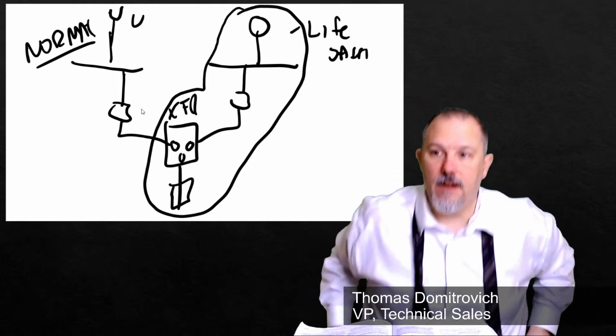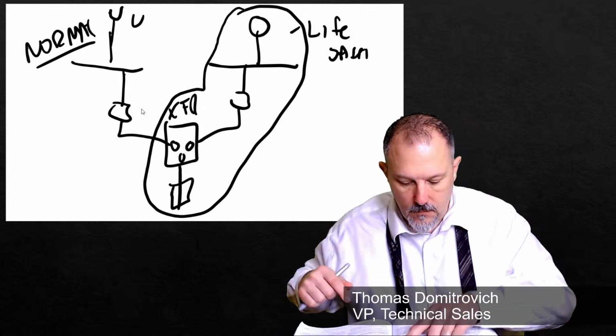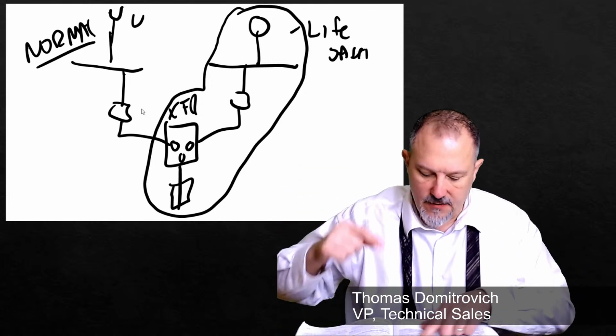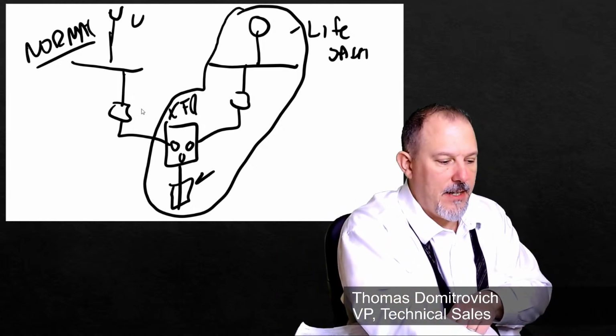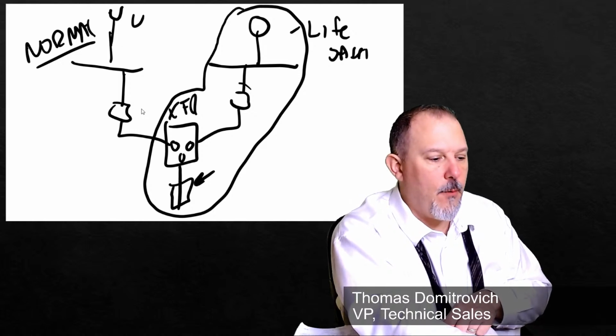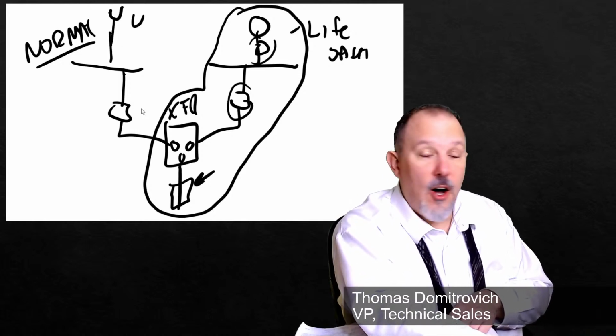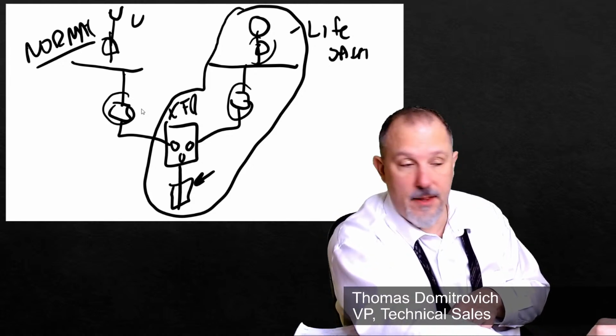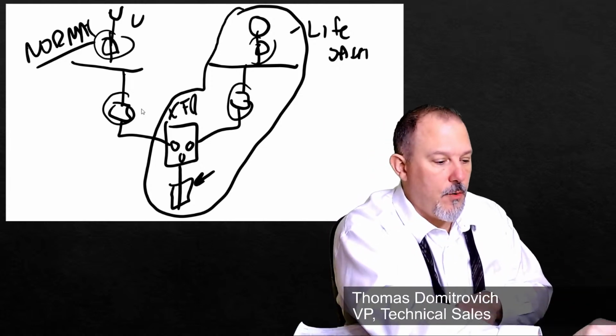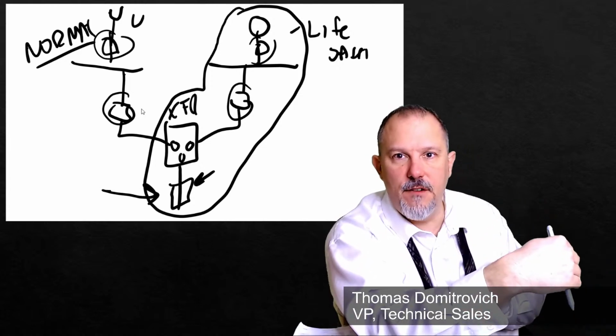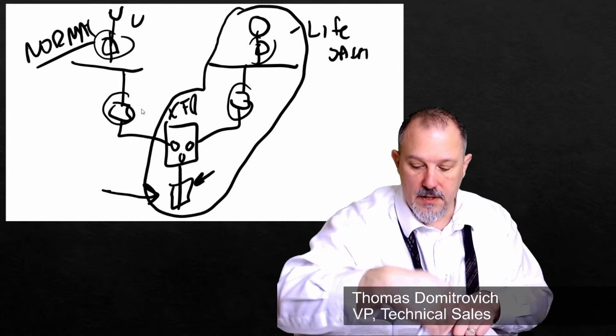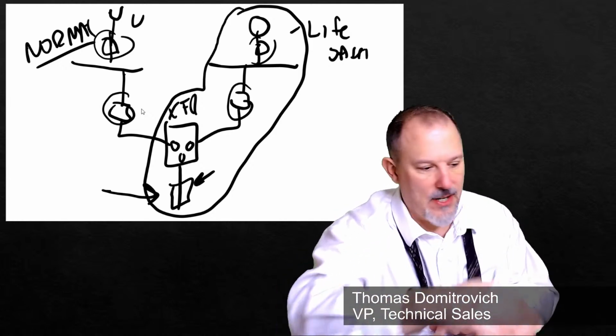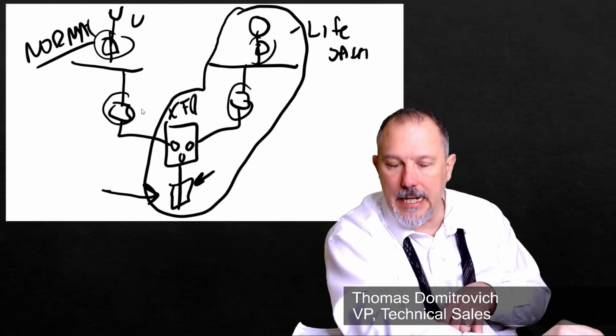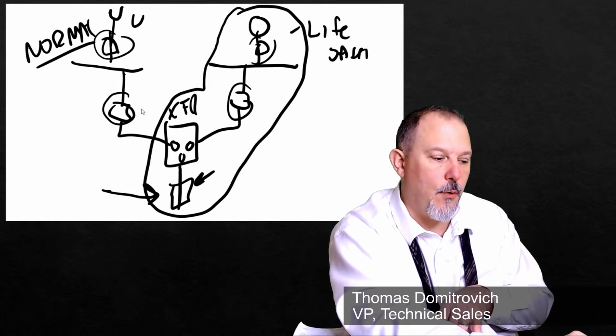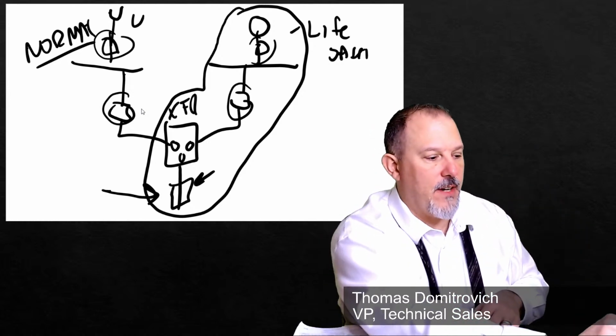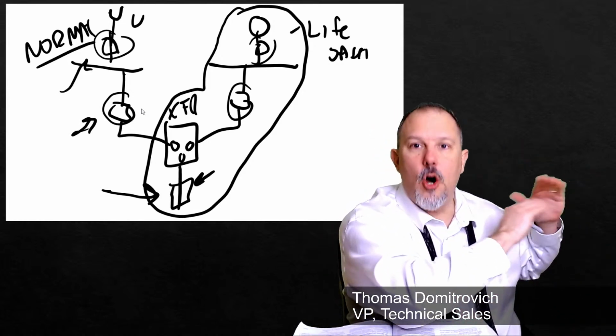Okay? Now, the way the language reads, it says that the overcurrent devices shall be selectively coordinated with all supply side overcurrent devices. This device, what are all supply side overcurrent devices? That would be this guy, and if there's one up here, that would be that guy. Also, that would be this guy, and if there's a main, which hopefully there is, it would be that guy. So this circuit breaker on the secondary of the transfer switch, which is on the life safety side, or the 700 side, 701 side, or the 708 side, this is in the life safety system, or it's on the legally required standby system side. The requirement is for that device to selectively coordinate with all upstream devices, which would include your feeder and your main on the normal side.